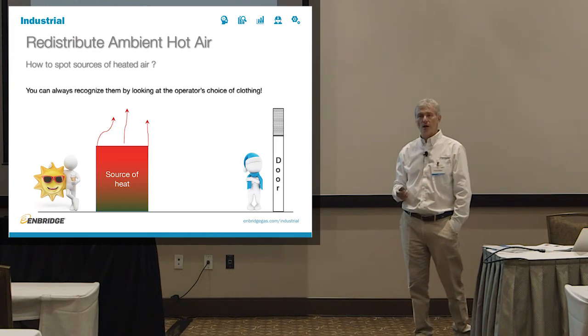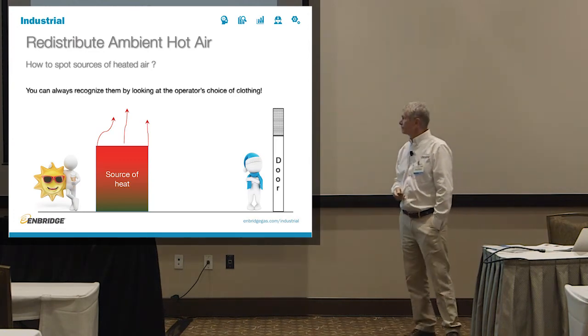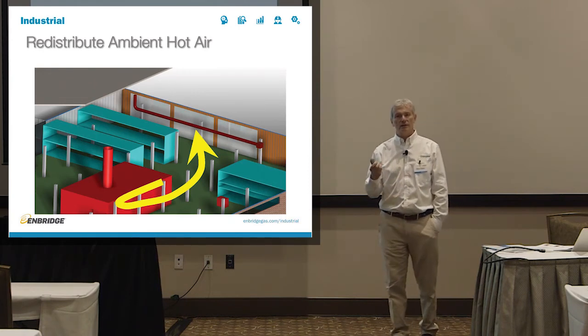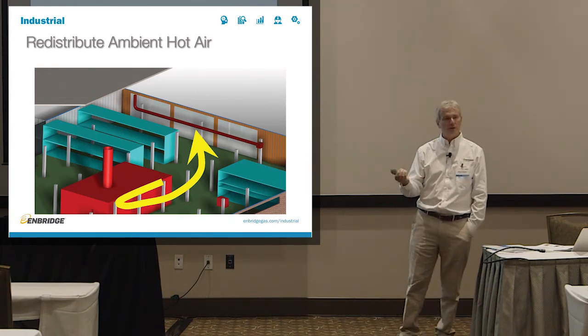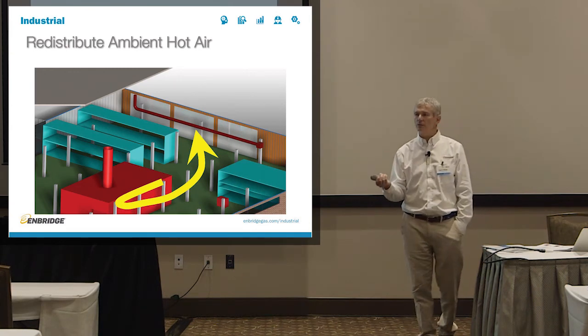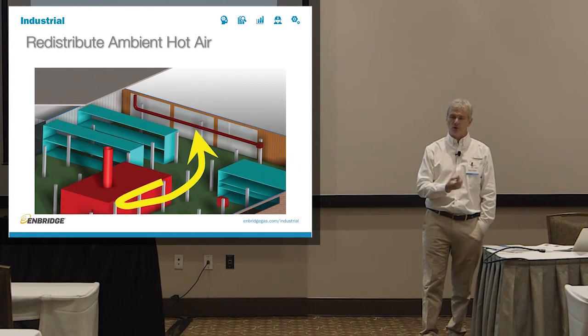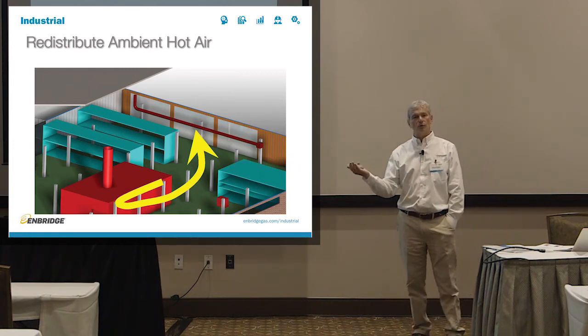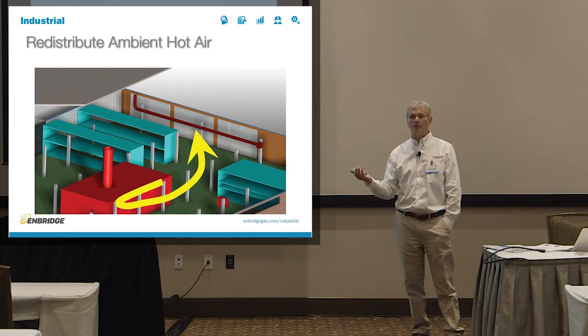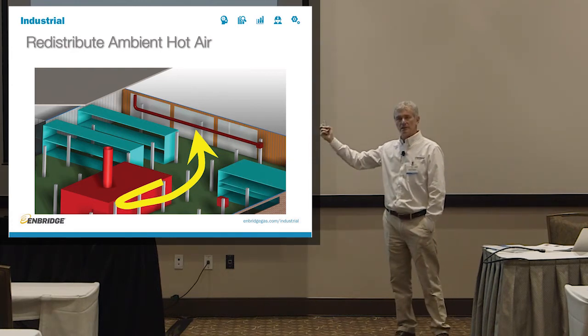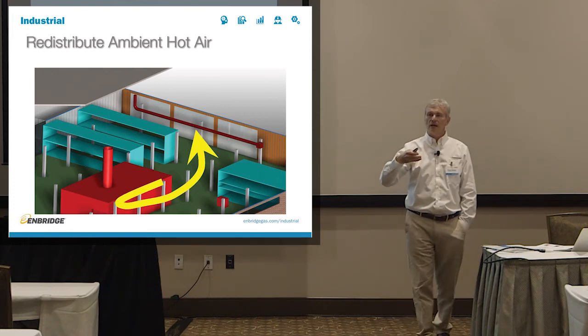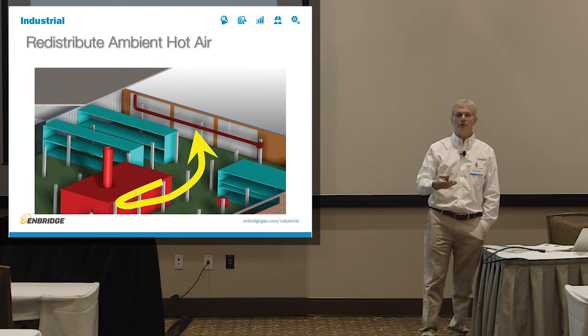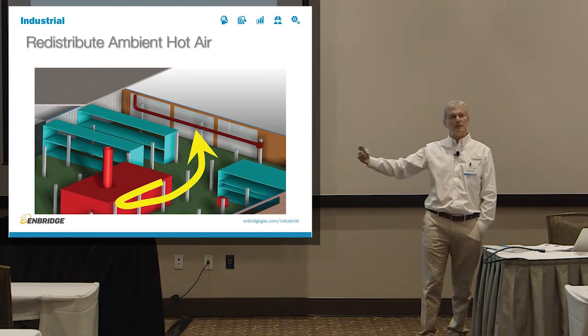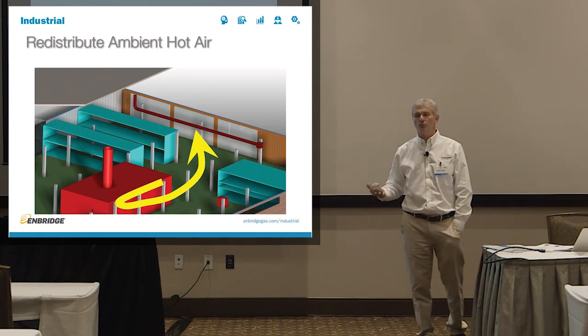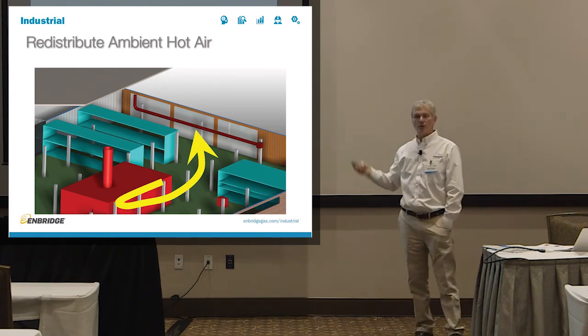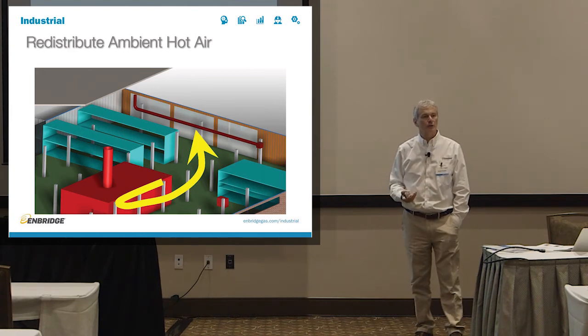So what can you do? How can you change that? How can you improve that? We want to take the heat that's concentrated around the heat source and push it away, inside the facility, to where we need heat to be. So we usually go from something like a process oven around the facility and into the shipping door area. It's a traditional way of doing it. Around the furnaces where I used to work, we had high heat furnaces and people could never get enough cold air. Even in the middle of winter, they would have their door next to the facility open, snow would fall in right next to the furnace, but they would be so hot. In the meantime, the guys at the shipping door who were doing the tow trucks, we couldn't get enough heaters to keep them warm.